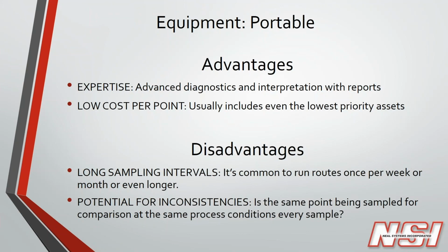The other disadvantage for portables is it's hard to get that sample. Maybe you can get it in the exact same location, but it's hard to get it at the same process conditions. And so if you're not taking samples all the time, it might be confusing if at one point you see the sample when the asset's working at a really high pressure or really high flow rate or something like that, versus when it's different conditions. So there's a disadvantage there for potential inconsistencies.